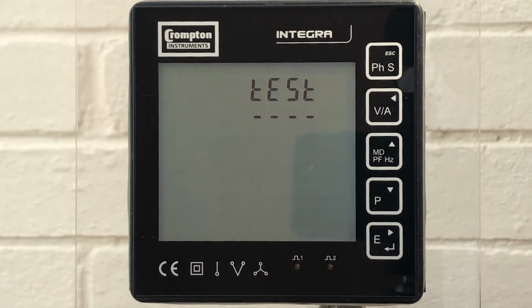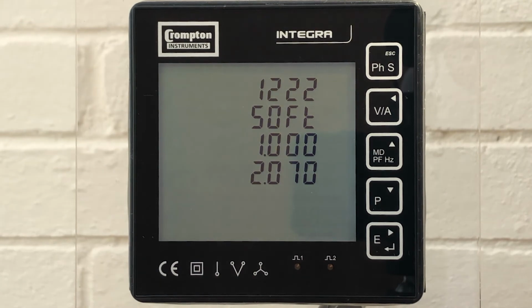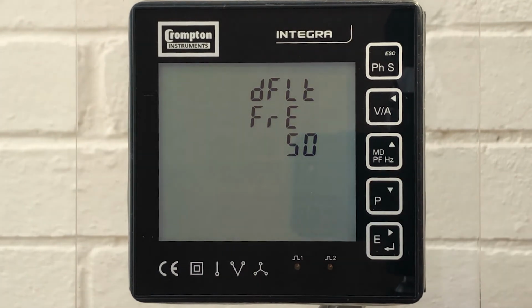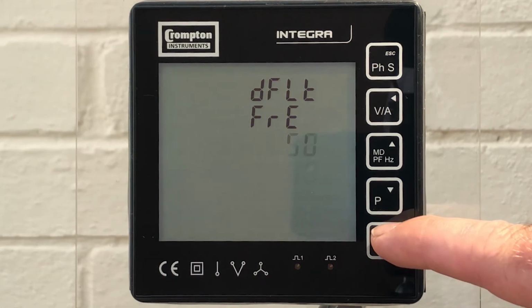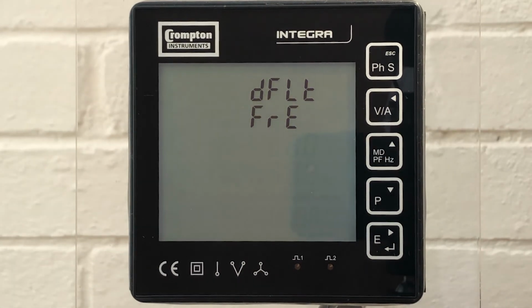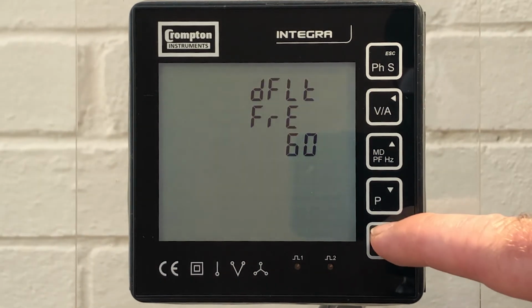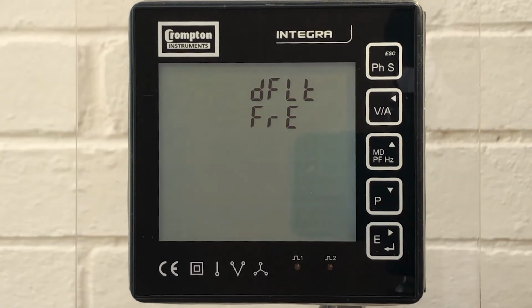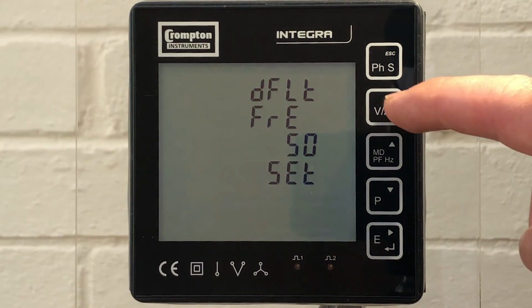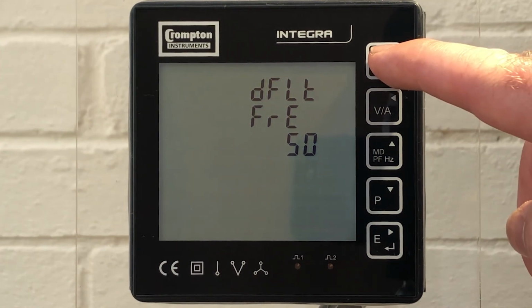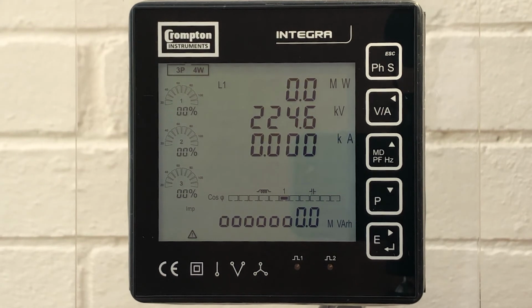If we escape using the VA button and arrow down to our next feature, this is the product software, and this details the product code and firmware version installed. We can arrow down to display the default frequency, which can be changed between 50 and 60 Hz. This brings us to the end of our setup, and if we hold the escape button for 2 seconds, you can see we're returned to the main screen of the Integra 1222, which is displaying the system power, voltage and current.